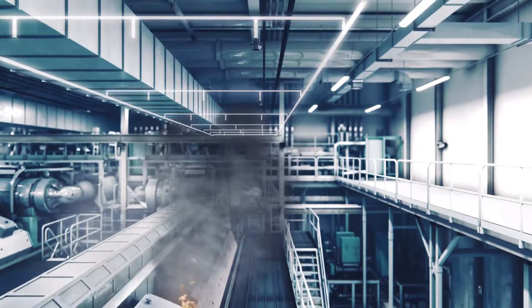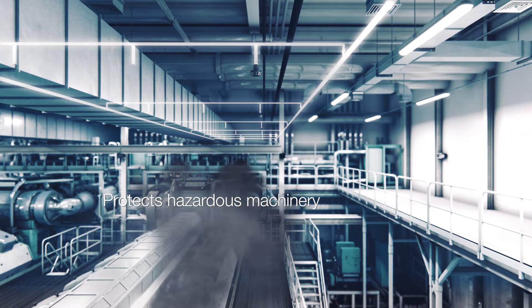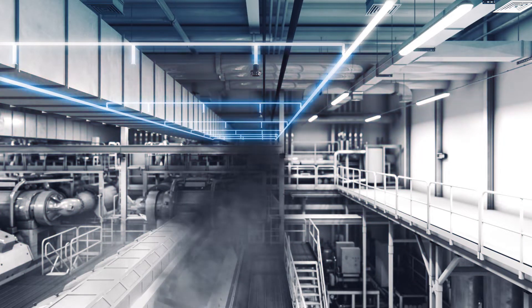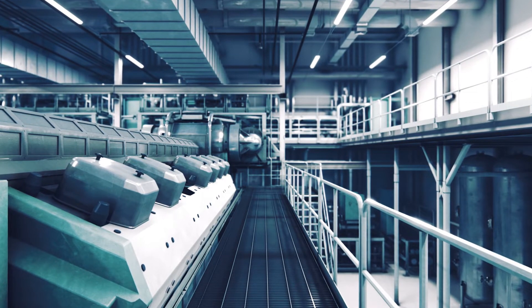HI-FOG spray heads are divided into sections so that each protected object has its own section valve. In the event of fire, HI-FOG is activated as soon as the section valve is released, either manually or automatically, through the fire detection system. Once activated, a signal is sent to the pump unit and water begins flowing through the system at high pressure, releasing fine water mist that quickly cools the source of fire and the surrounding area, preventing the fire from spreading.